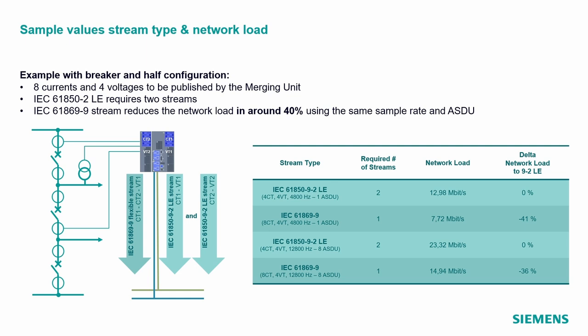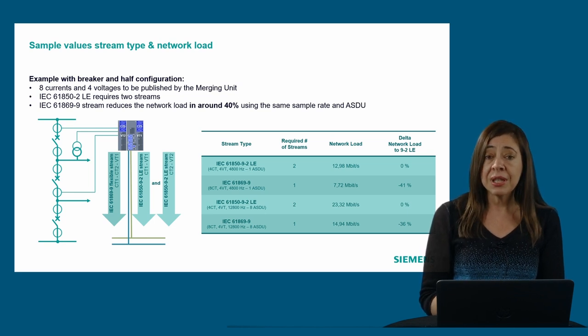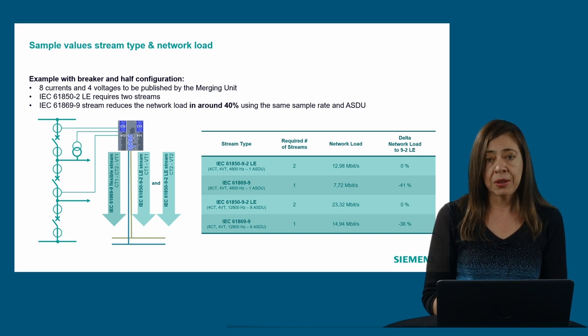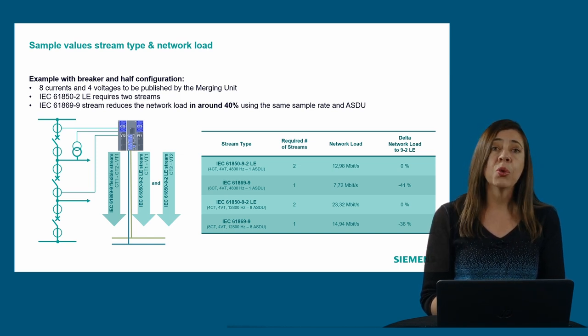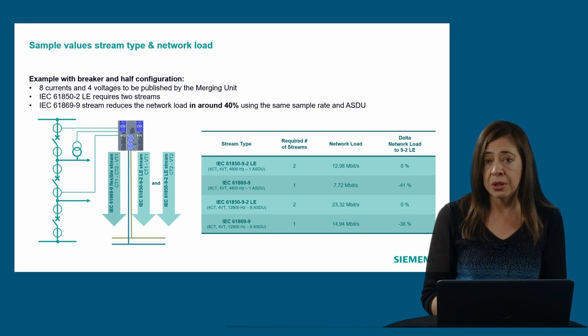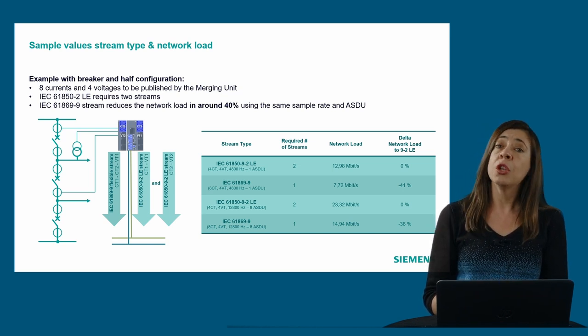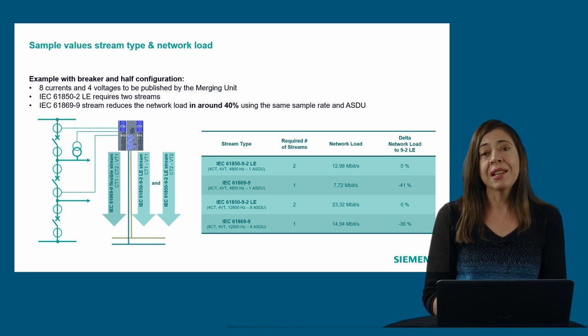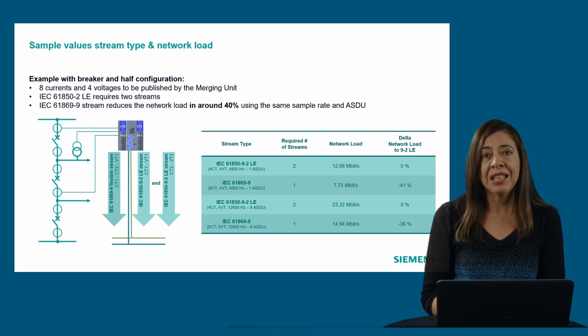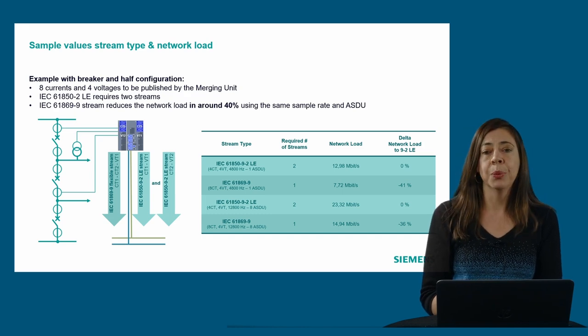And that means if we use the 4800 Hz sampling rate with light edition and the 2 streams, we use almost 13 megabits per second of the bandwidth. But if we use the flexible stream, then we reduce this to less than 8 megabits per second, which means almost a 40% reduction. That's why our recommendation is using the flexible streams to take advantage of the complete bandwidth in your process bus network.